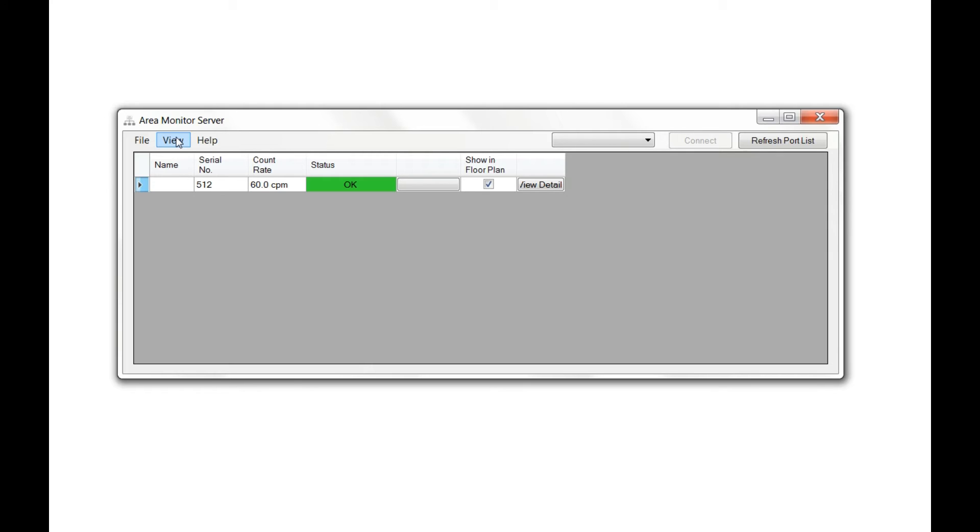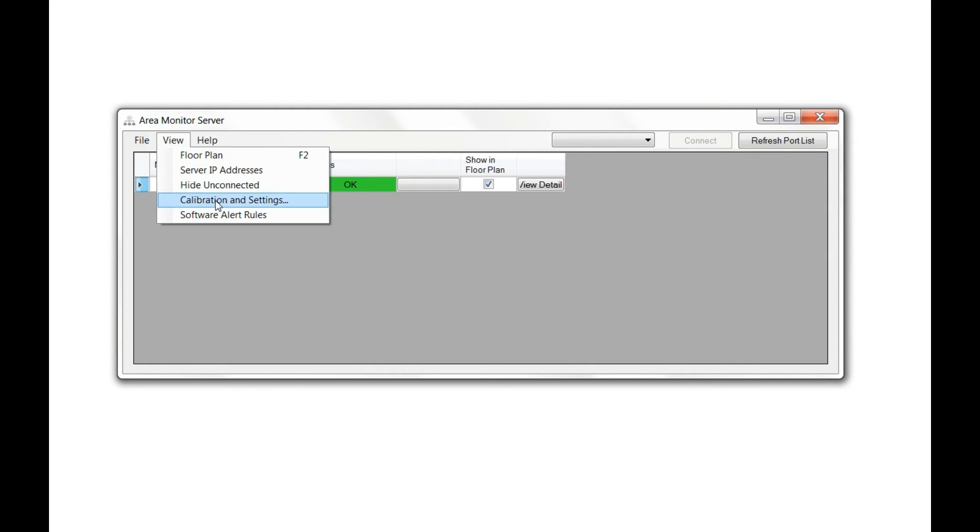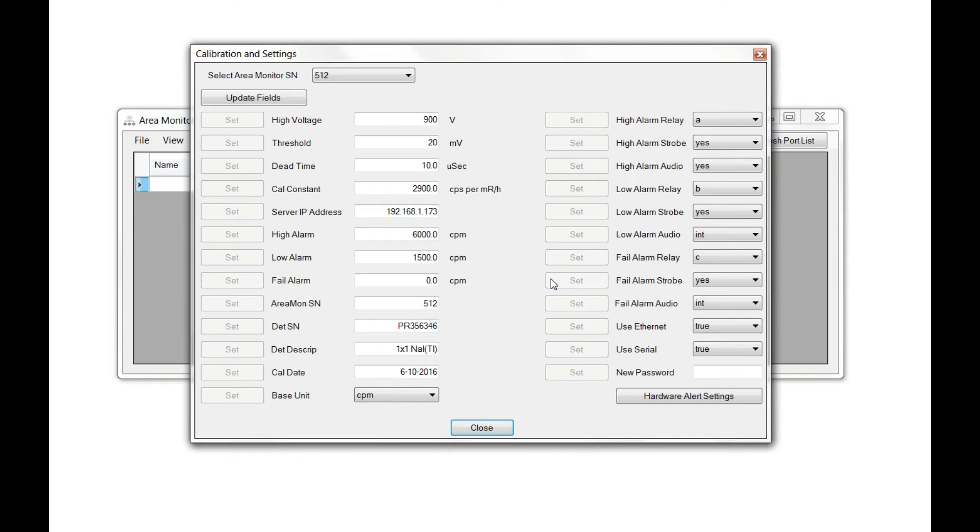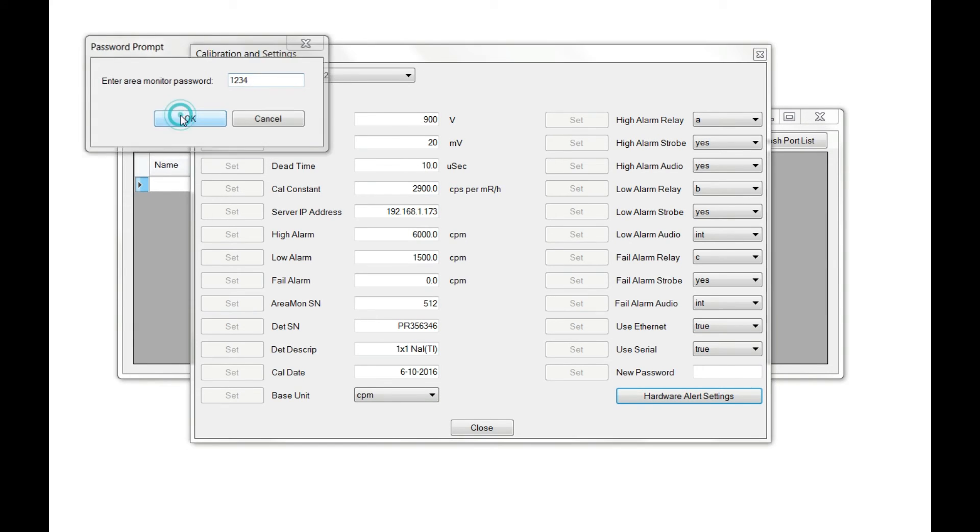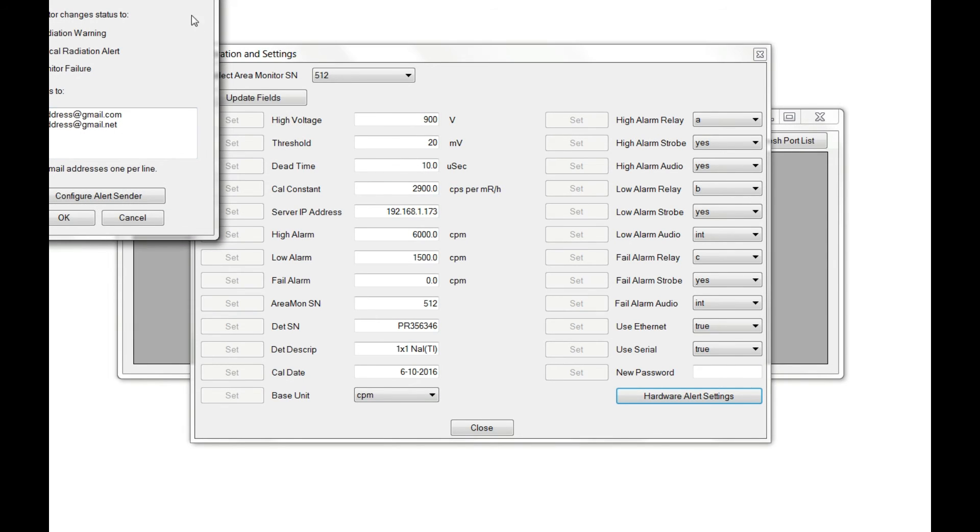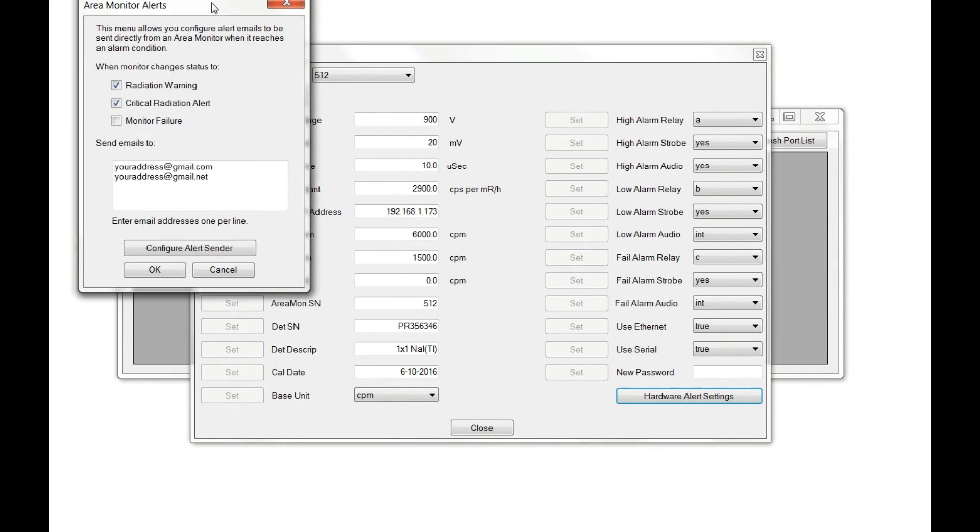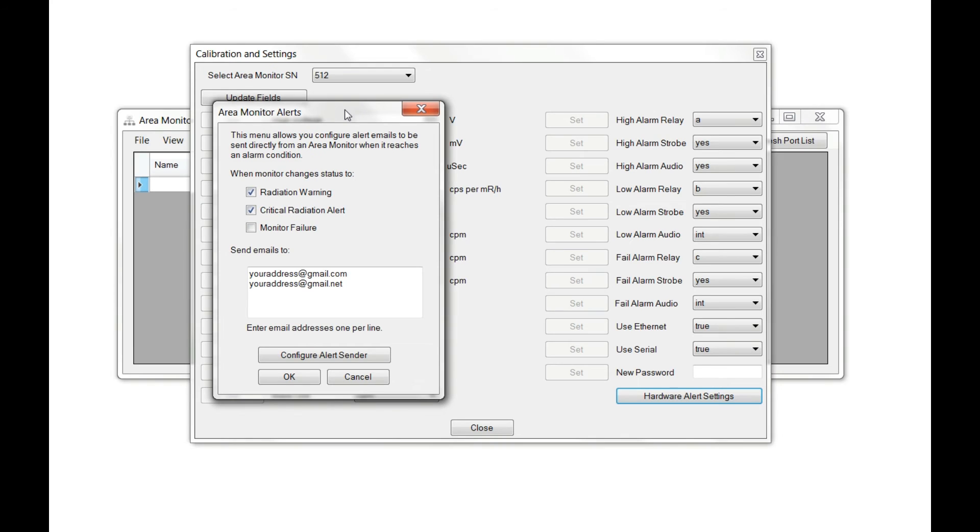To set up a hardware alert, go to View, then Calibration and Settings. In the lower right-hand corner of the Calibration and Settings window, click Hardware Alert Settings. You'll be prompted for a password. Enter your password and click OK. You'll now have access to setting up hardware alerts in the area monitor itself.